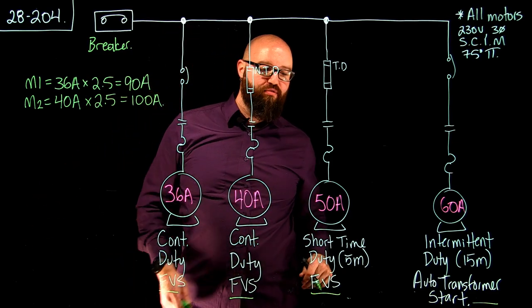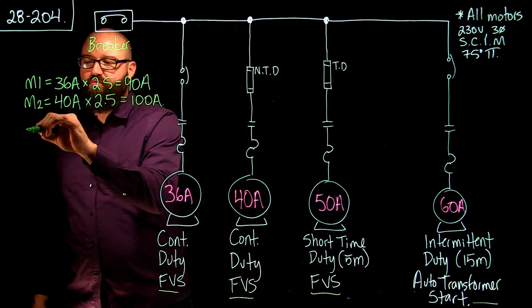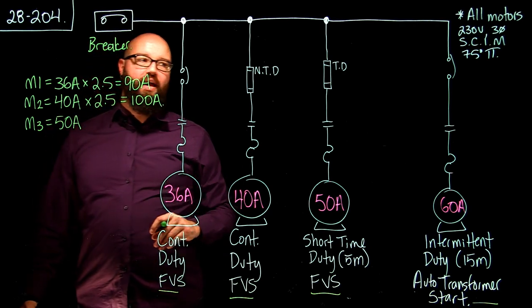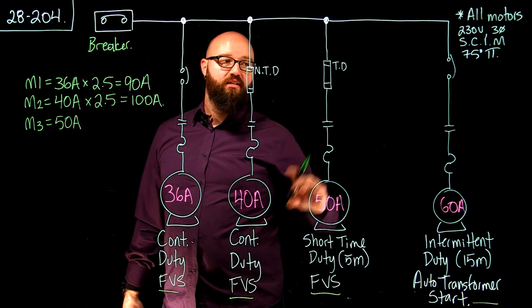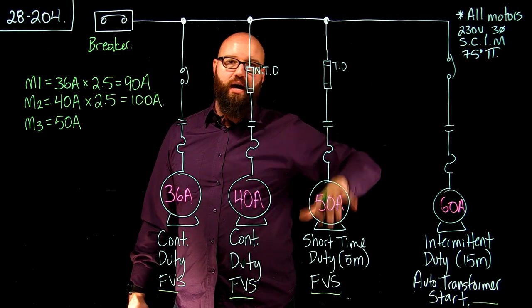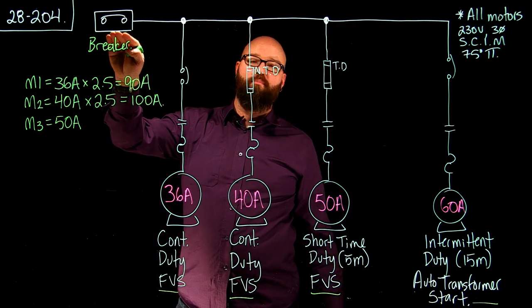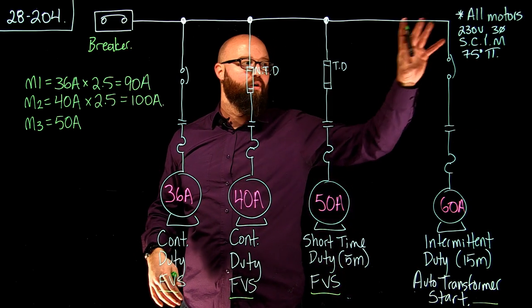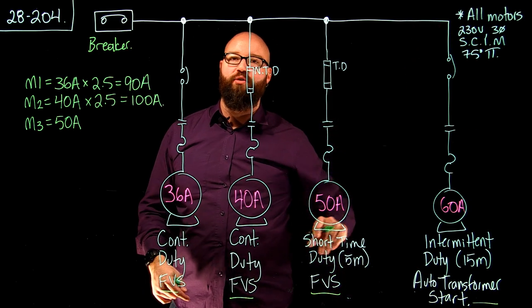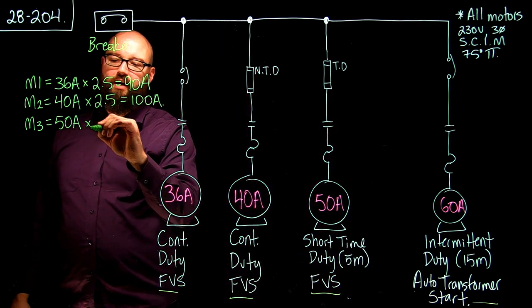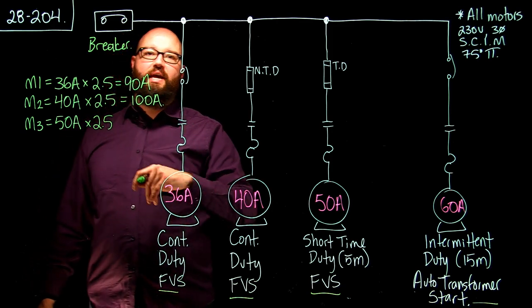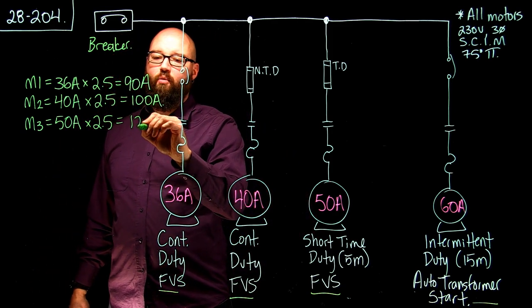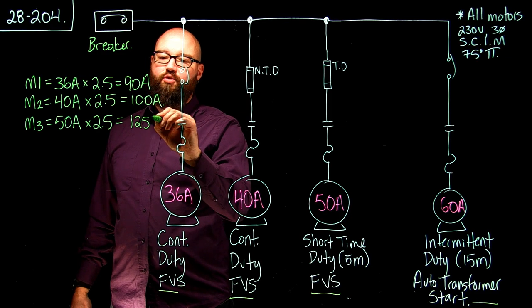Moving to Motor 3: we're going to take our 50-amp FLA. Even though it's protected by a time delay fuse on the branch, I don't care. I'm going to apply the multiplier for a breaker from Table 29 for that particular motor. So 50 amps times 2.5 — because it's a squirrel cage induction full voltage start, three-phase — we end up at 125 amps.